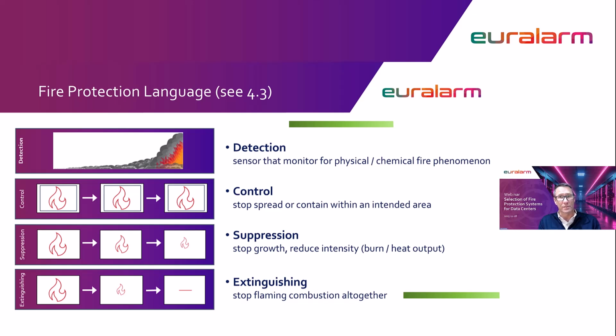Fire extinguishing systems, exemplified by gaseous technologies, do extinguish. They're highly effective and leave no residue, which makes them suitable for use in sensitive environments and where full cover is necessary, i.e. extinguishment penetration of the IT equipment so that the business can operate, possibly uninterrupted, but that comes at a cost.